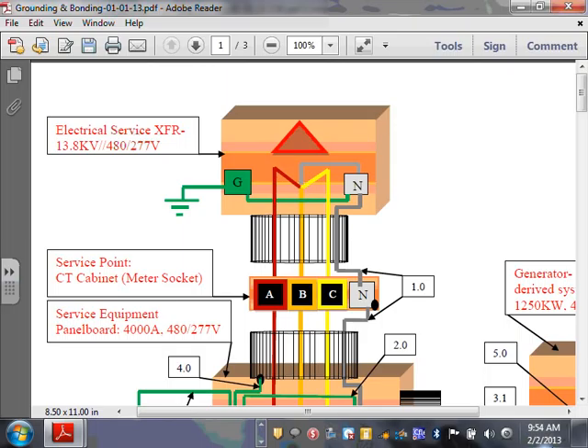So anyway, any comment, guys, about how the system is put together here? Now from the termination box, the CT cabinet, the meter socket, it could be a meter socket, termination box, CT cabinet, any of these, from here you pull the neutral only. You bond the neutral to the frame, so you can ground the frame of the box. You must bond and ground the frame of a box, the termination box. Then we enter the switch gear. When we enter our switch gear, how many conductors are we pulling for a three-phase system? We're pulling 4 conductors. If your system is a delta, you're pulling 3 conductors. Delta ungrounded, you're pulling 3 conductors. The only thing that's going to drop is that gray one.